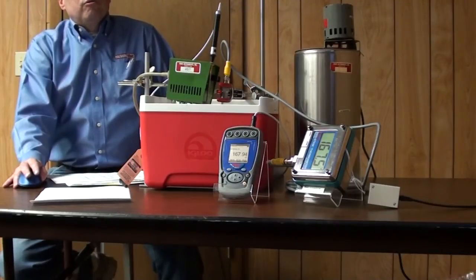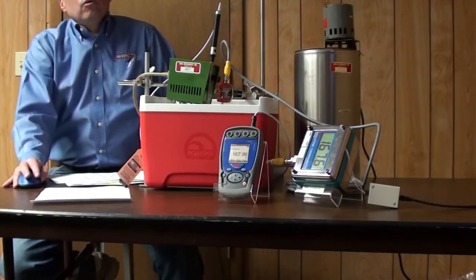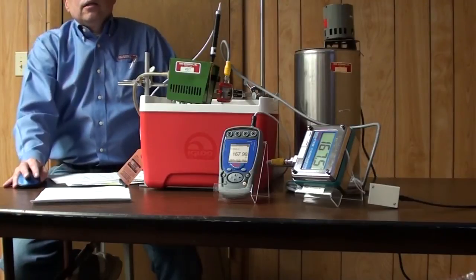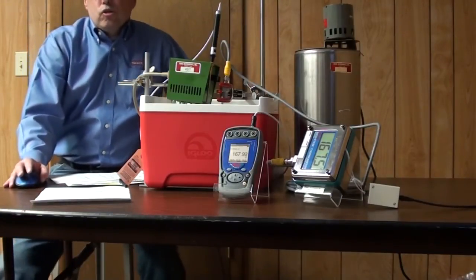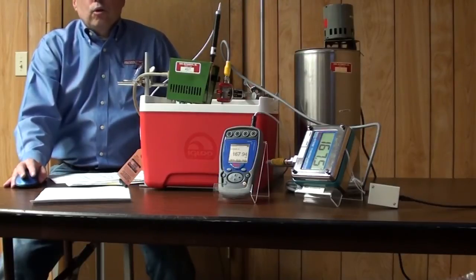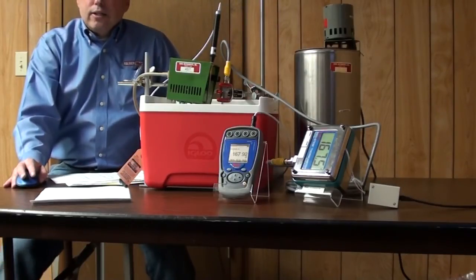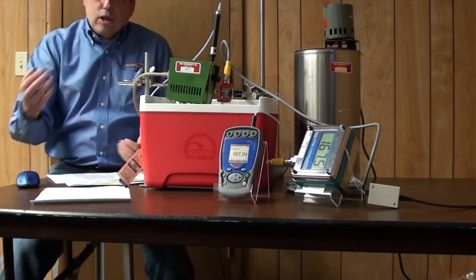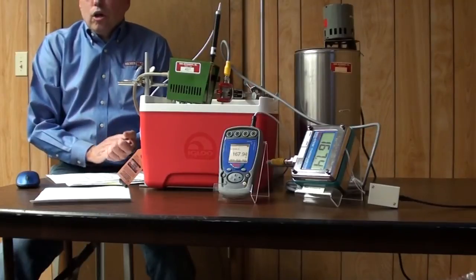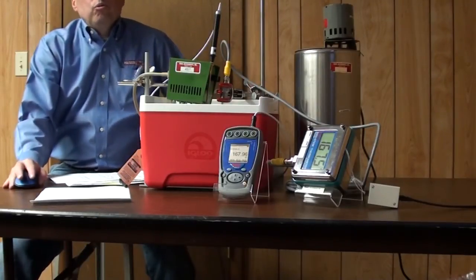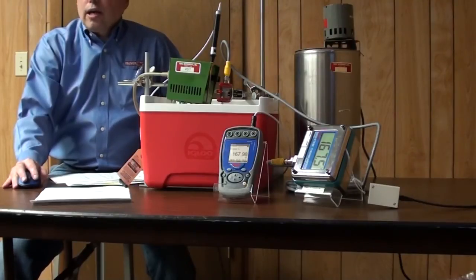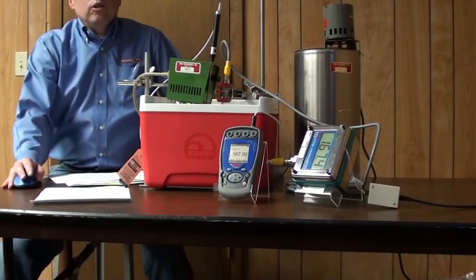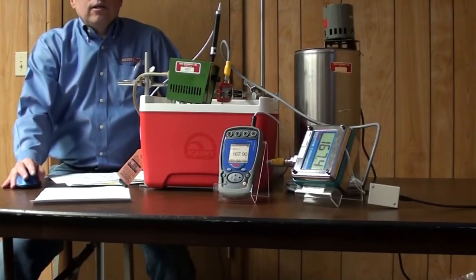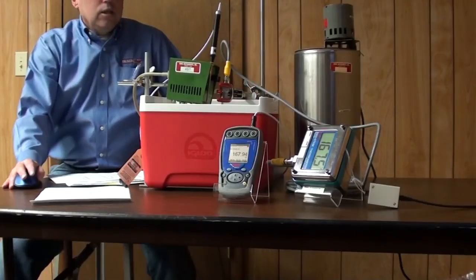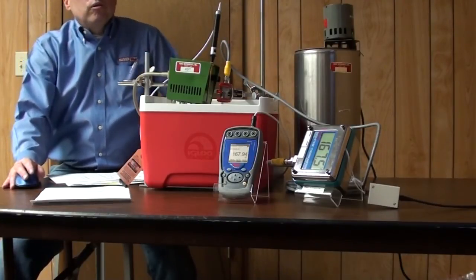And then afterwards you look for a tolerance. Does it meet tolerance or not? And is it in or out of tolerance? With our unit, as I said, it's 0.3 of a degree that is the allowable deviation. So even though you've used this a year, it should be within 0.3 of a degree. For the after data, we usually tighten those specifications after adjustment because that's when we're first sending the instrument out to you. So we want to make sure that there is still some room if that unit does have some change in it over that next year's period. And then the after data is really the same type of thing, only you would have done the adjustment, which is what we'll demonstrate.